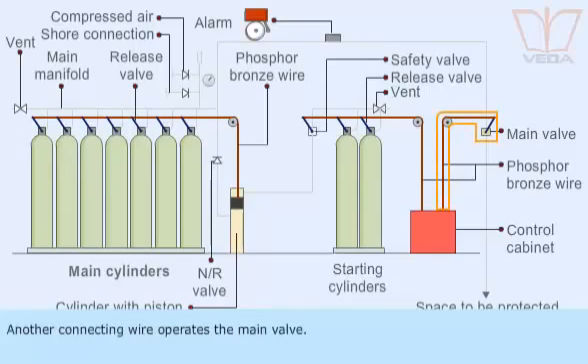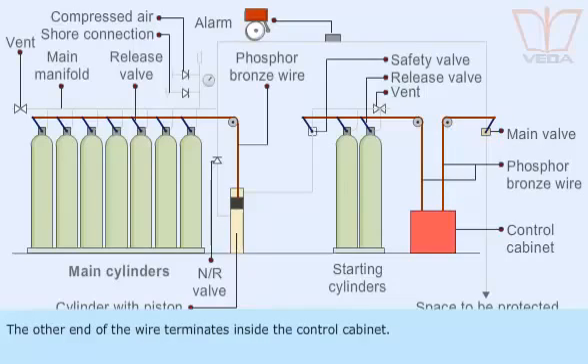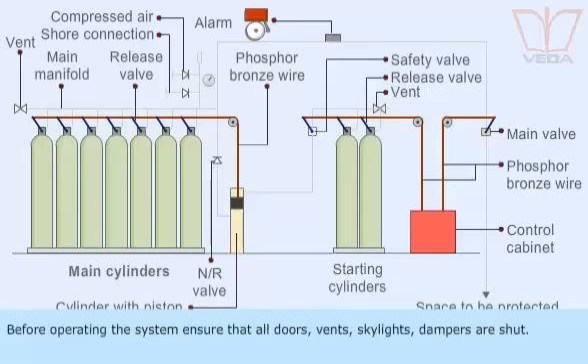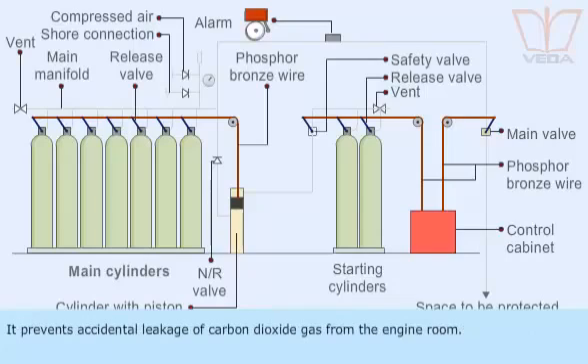Another connecting wire operates the main valve, with the other end of the wire terminating inside the control cabinet. Before operating the system, ensure that all doors, vents, skylights, and dampers are shut. This prevents accidental leakage of carbon dioxide gas from the engine room.